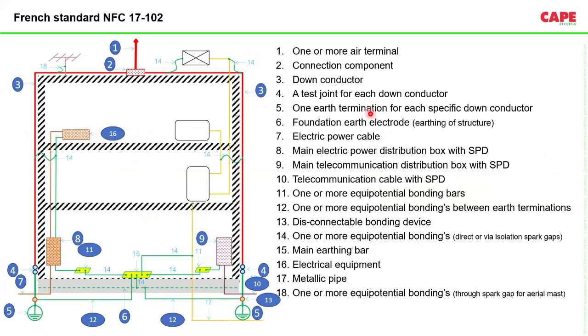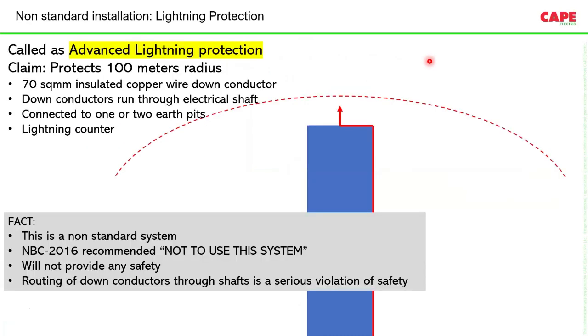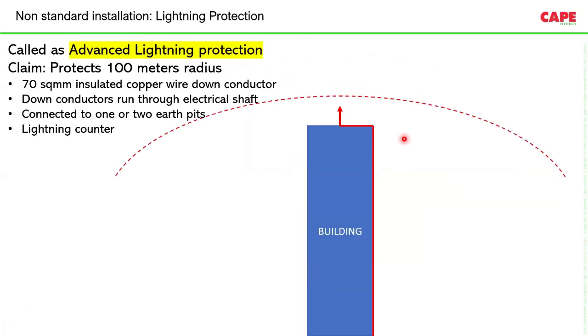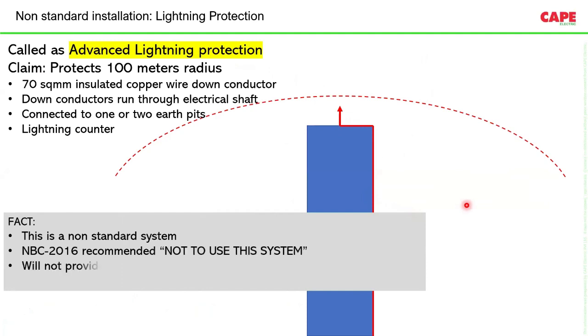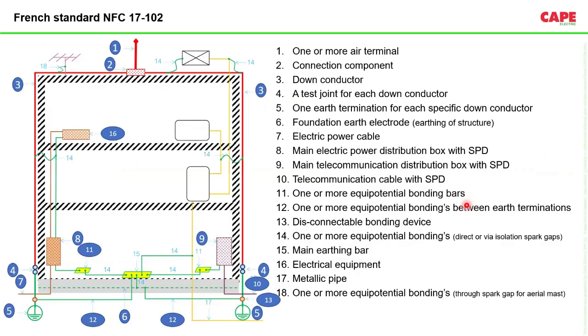The French standard explains the system in detail. You need to have several safety measures in a building. Over and above, you see this item number 1. This is the ESE rod. So basically, you need to have serial numbers 1 to 18. If you go as per the Indian standard IS IEC 62305, you can achieve safety by using items serial number 2 to 18. Item number 1 is absolutely not required. Whereas the French code is asking to put an additional rod. Please note, an additional rod. Whereas the same system, manufacturers take it to India and they say that one rod protects 100 meters. You take one wire and connect it to the earth pit, and your lightning current will go like water through a pipe, which is absolutely wrong.